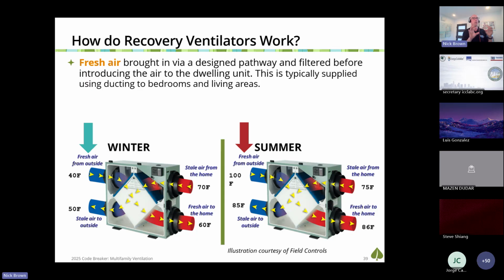So you see how that benefits your HVAC system, because this could be 50 or 100 CFM operating continuously that your HVAC system doesn't have to heat or cool. In summer, on a 100-degree day, that 100-degree air, which would be coming in at 100 degrees in a supply or exhaust ventilation scenario, now comes in at 86, let's say. So there's the energy savings part.